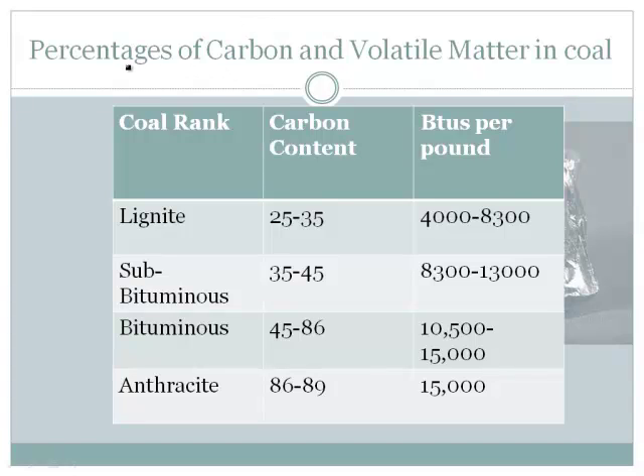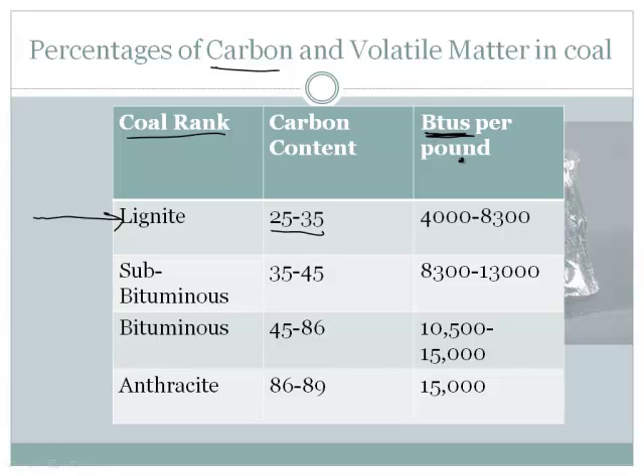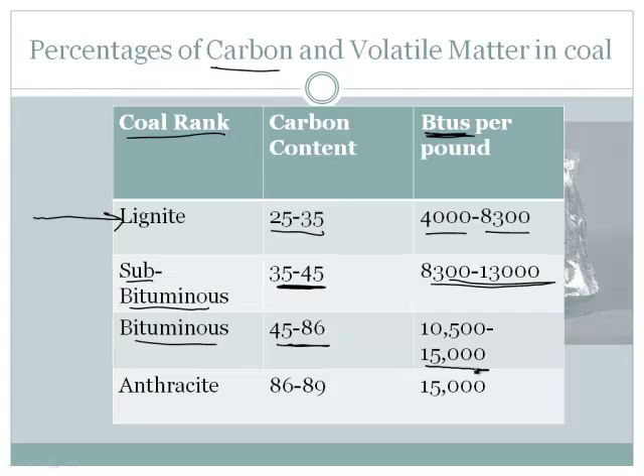Here are the different varieties of coal. There's lignite coal, with 25% to 35% carbon content and 4,000 to 8,300 BTUs per pound. Then there's sub-bituminous, with a higher percentage of carbon and more BTUs per pound. There's bituminous coal — even higher, giving about 15,000 BTUs per pound. And the best coal is anthracite, with 86% to 89% carbon and about 15,000 BTUs per pound. Of course, when burning coal you want the coal with the highest energy content. However, that's not the only consideration — you're also looking for what's called clean coal.